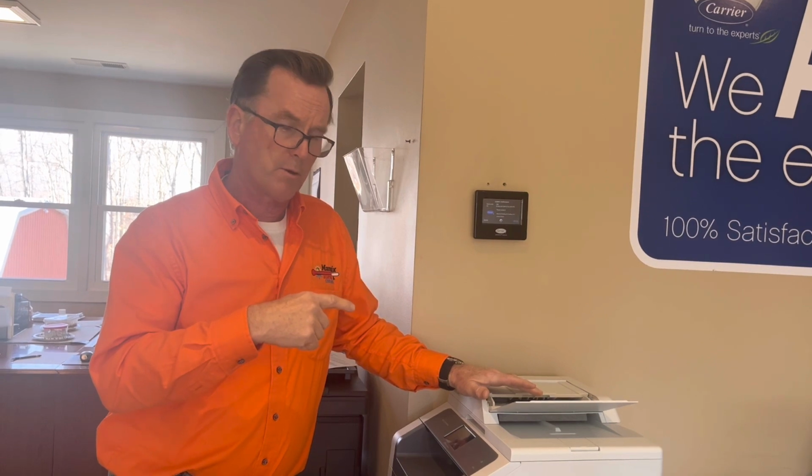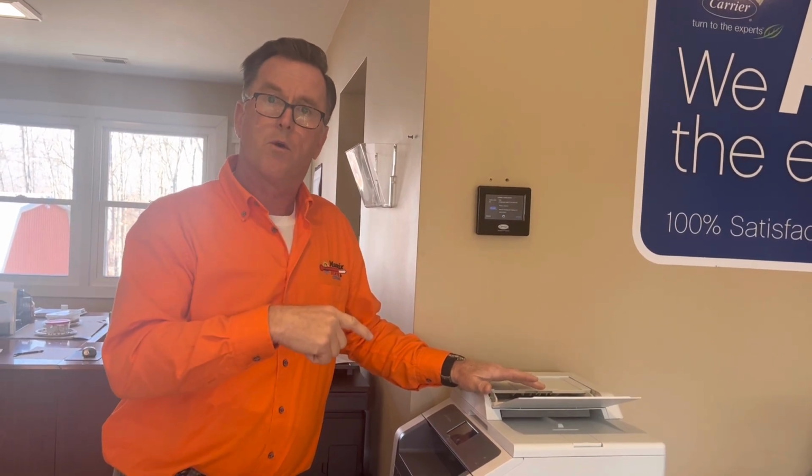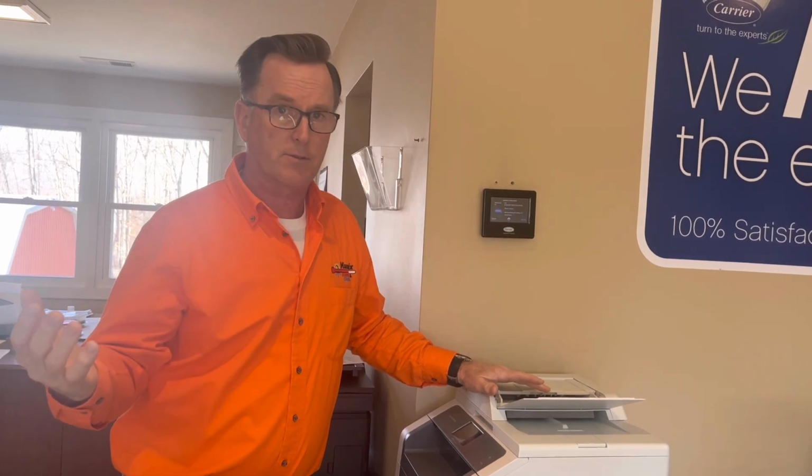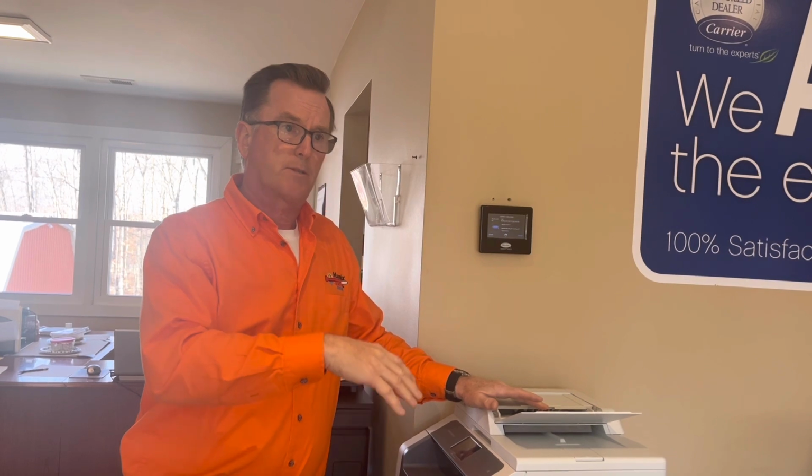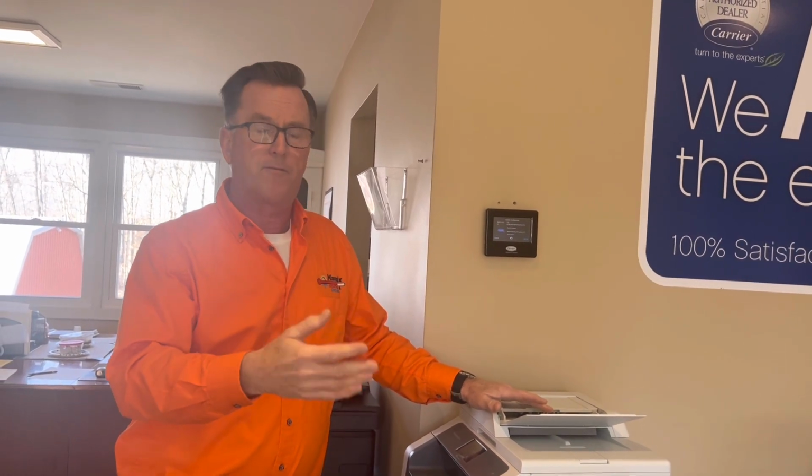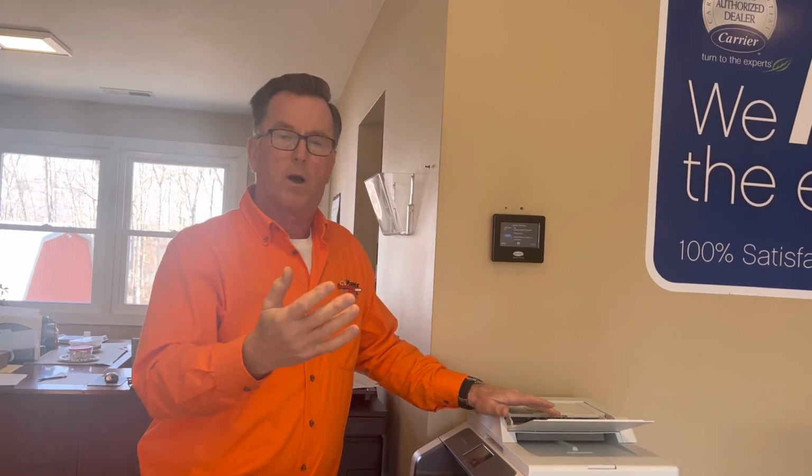One of the other times you'll get this, if you're getting this same fault during the wintertime, you may see it in conjunction with a limit fault. And that is usually a result of a dirty filter. If the filter blocks the air through the system, it causes the furnace to run hot. If it gets above the limit, which is usually about 185 degrees, you'll wind up with a limit fault. And that too will throw that same fault code.